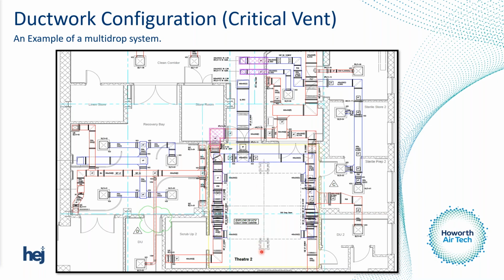And then if you were to put a mirror down the center of the canopy, you've almost got complete symmetry, with the exception of this coming in at the center. You can see that these ductwork connections here are the same at the top and the bottom, and you have VCDs for each position at each corner of the ventilation system. So we could take a total traverse within the plant room upstairs to calculate for the operating theatre. And then another thing that you can get within UCV operating theatres is the canopy having an impact on the rest of the ventilation system.